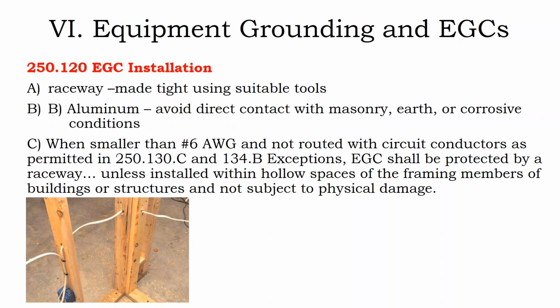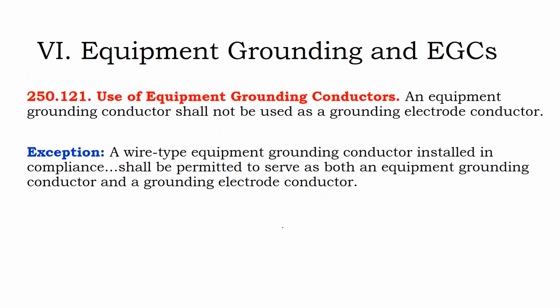So you can run equipment ground conductors when it's number 8 through the framing members of your structure. What that might say is, if you're going inside the rooftop, inside the building, to ground your system up to the rooftop, then maybe you're using a number 8 with a green jacket rather than bare number 6 when you stay outside the building, so that you can run it through your framing members. And what I usually do is just put the number 6 in the conduit, an oversized conduit.